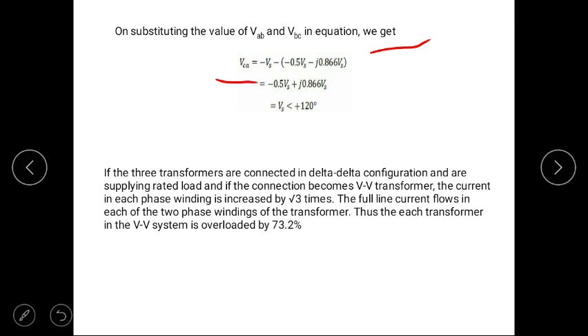Now if the three-phase transformers are connected in delta-delta configuration and are supplying rated load, and if the connection becomes a VV system, the current in each phase winding is increased. The full line current flows in each of the two phase windings of the transformer. Thus, each transformer in the VV system is overloaded by 73.2%. These are the different types of connections of a three-phase transformer.